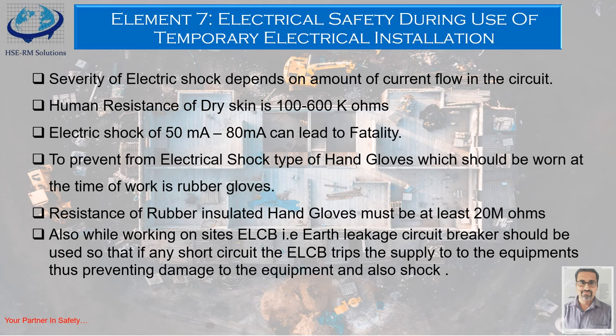The severity of electric shock depends upon the amount of current flowing in the circuit. Human resistance of dry skin is 100 to 600 kilo-ohms; sweating changes this resistance. Electric shock of 50 milliamperes to 80 milliamperes can lead to fatality. To prevent electric shock, rubber hand gloves must always be used, and they must have at least 20 mega-ohms of resistance. Also, while working on site, an ELCB — Earth Leakage Circuit Breaker — should be used so that in case of any short circuit, the ELCB trips and cuts supply, preventing damage to equipment and preventing shock.